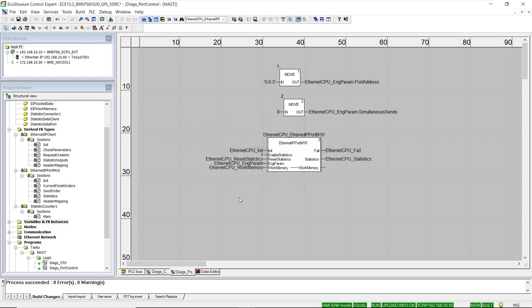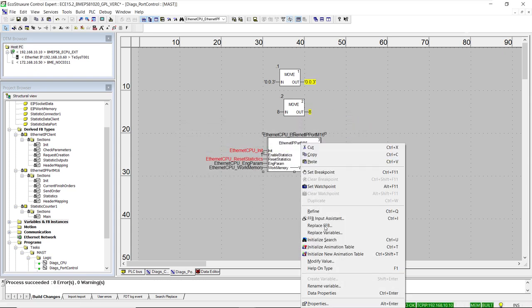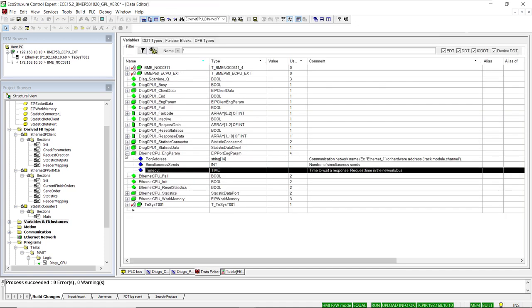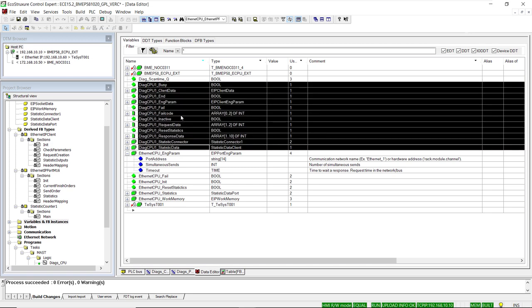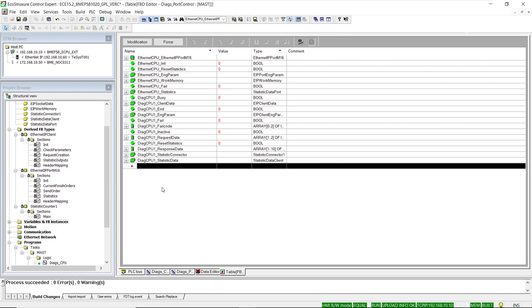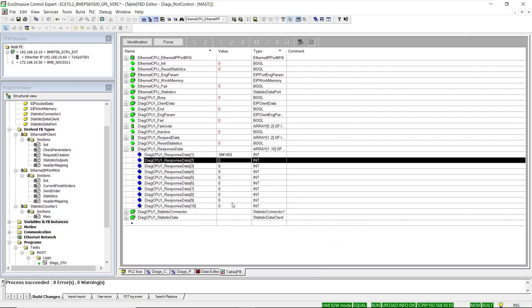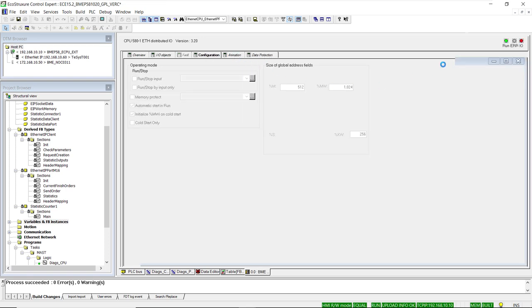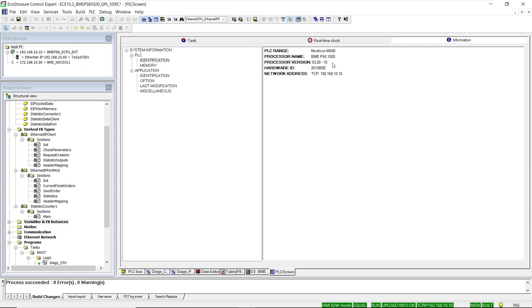Once the program is downloaded, we create an animation table to monitor results by right-clicking on the port function block. We paste the DiagCPU1 variable names into the animation table. In the response data, we see hexadecimal values: 14 (which is decimal 20) and 03, corresponding to major and minor firmware revisions — so firmware version 3.20. This can be confirmed on the animation tab of the CPU while connected online.